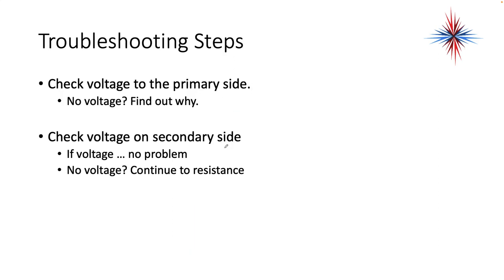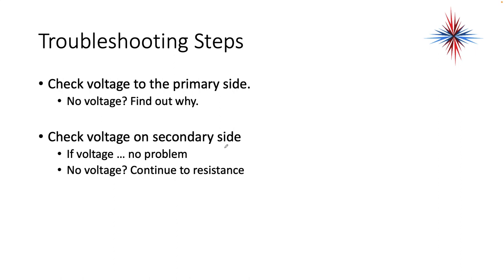Troubleshooting steps for transformers are actually pretty easy. Check voltage to the primary side — if you don't have voltage coming to the transformer, find out why. No sense going further if you don't have voltage. Check voltage on the secondary side; if you have voltage, there's no problem with the transformer. If no voltage, lock out and tag out the system and isolate the transformer primary — disconnect it from the rest of the circuit. Check the resistance of the primary winding: if O-L or infinite, the winding is open; if zero, the winding is shorted. Either way, you have a bad transformer.